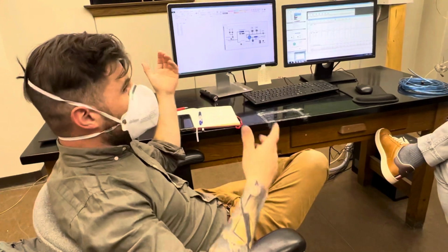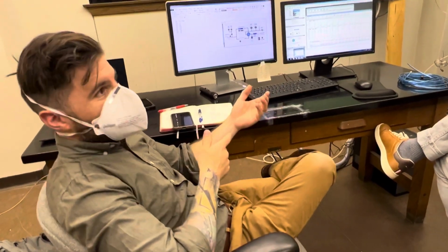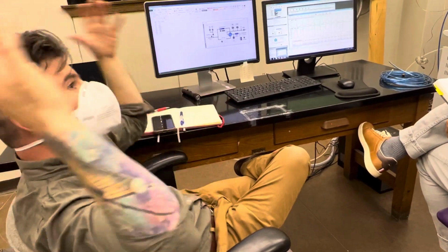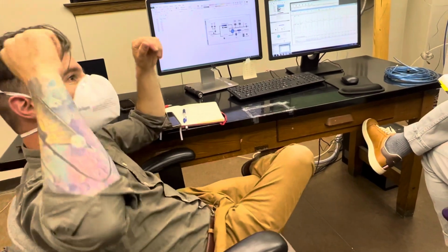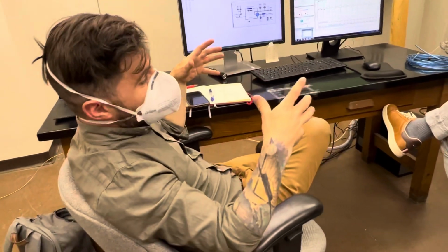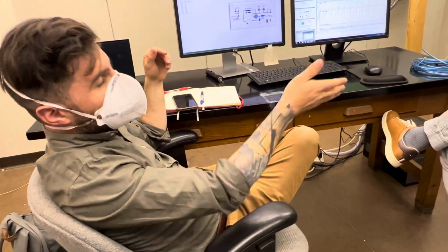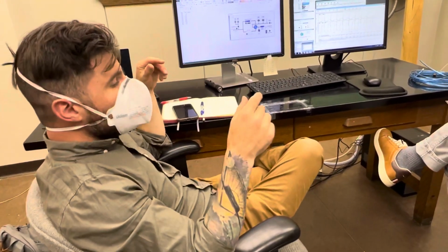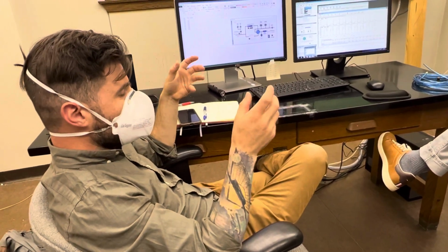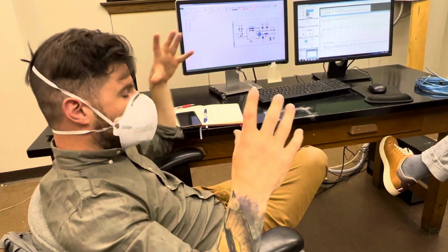So when the gas gets inside the source, it's being attacked by an electron machine gun. Like you enter a room as gas and you're getting shot at by electrons. Some of your electrons fire off and you become ionized. That happens to all the gas in there. So sometimes you're getting excess hydrogen that becomes ionized instead of the deuterium, and that comes together and goes through. The way the source is organized, there's a box and a trap, and the electrons are flowing through and getting captured.